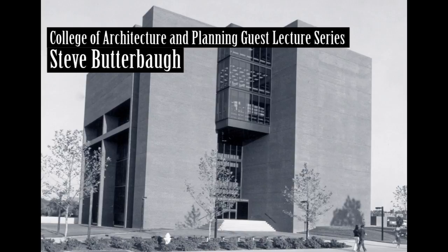With this level of familiarity of the building, we went to the real building to see how it corresponded to the information we had. Walls were often shifted or removed. Windows and doors were often removed. Exterior walls sometimes had insulating materials such as paneling added. Upper floor ceilings were often recently insulated. Sometimes dimensions were different than what was shown, or an addition had been made to the building for which we had no written record. Storm windows or thermal pane replacement windows were sometimes added.